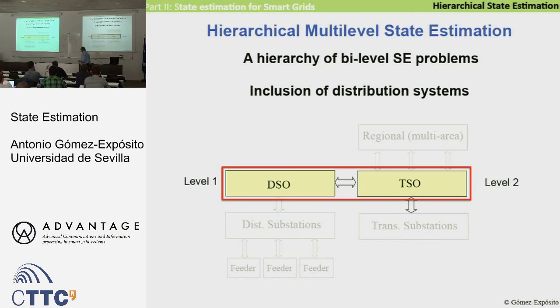Distribution systems—the distribution system operator, distribution utilities basically—they have control centers and a very similar energy management system to transmission system. For instance, in Spain, both the transmission operator and distribution utility mostly have a Siemens system, so state estimation, similar systems. What changed is the redundancy and the kind of information they are using. But yes, they have currently a state estimator, and they use an external equivalent of the transmission system to perform this state estimation. So distribution companies have a small equivalent provided by the transmission, so they can run their state estimator. So they are doing this.